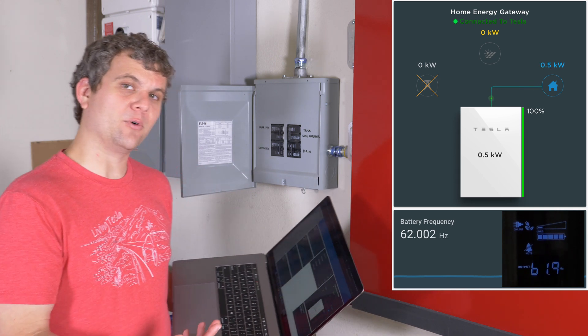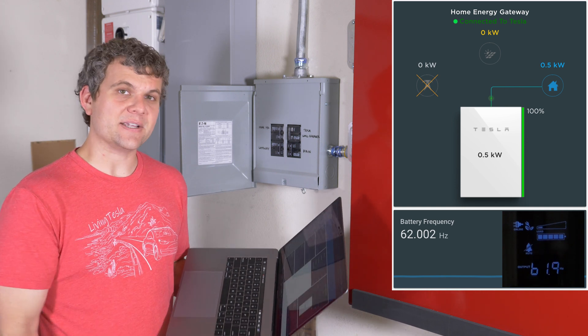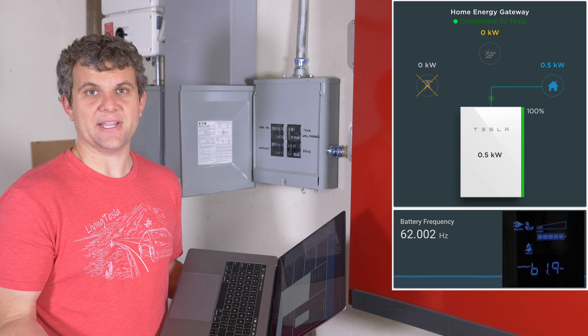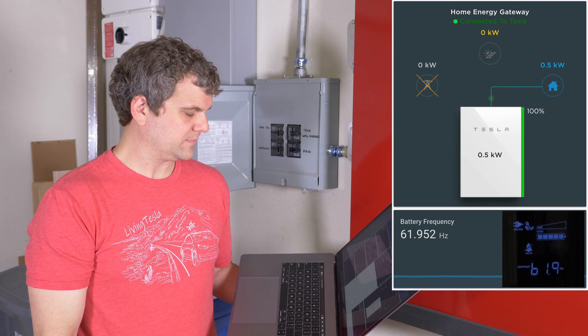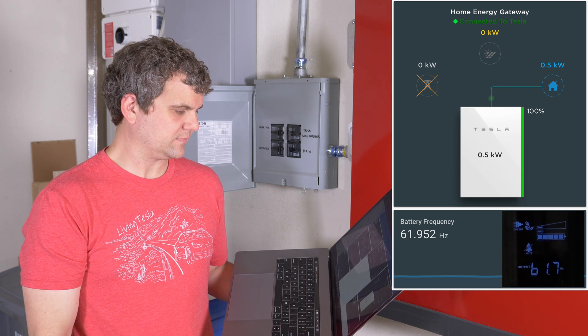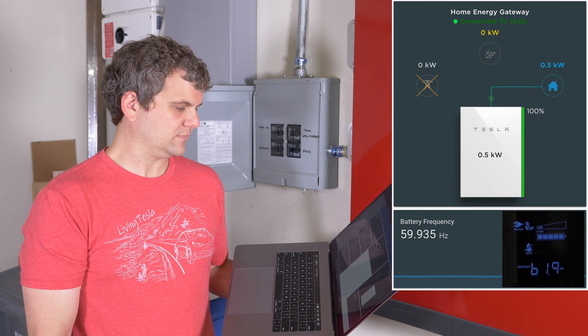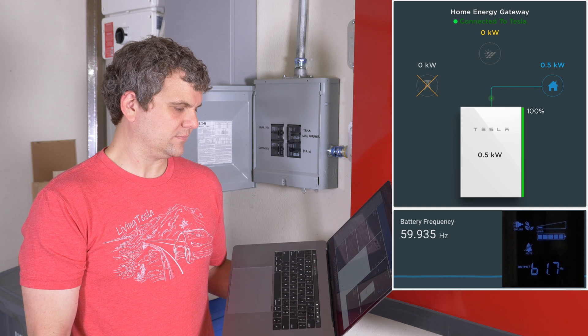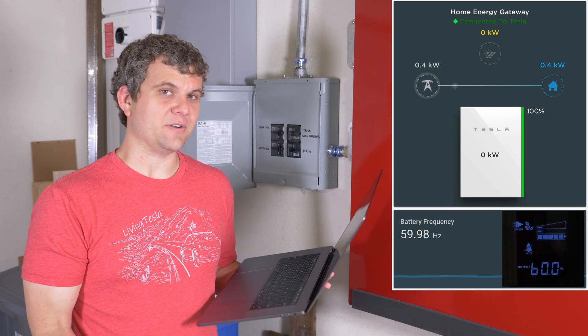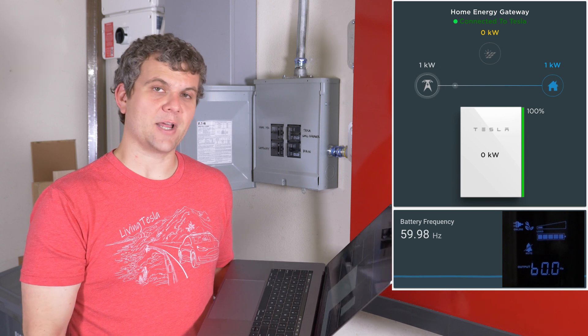So let's turn the power back on, reconnect the grid. And we should see that battery frequency come back down as the Powerwall is telling solar, hey, I can get some power again. So, there we go. We're back down to 60 hertz. Everything's working like it should. Never saw a loss of power on the UPS and everything's coming back online.